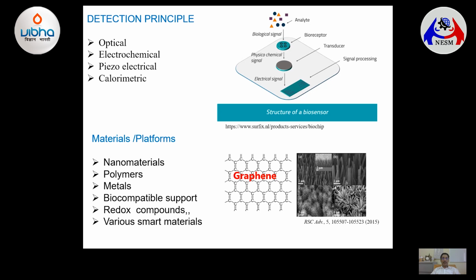This signal may be optical, electrochemical, piezoelectric, or calorimetric, and it is ultimately transduced to an electrical signal, which is then processed and finally appears in digital form to show the quantity of the analyte present in a sample. Based on the type of transducer, biosensors are generally classified. There are basically four different kinds of transducers. One is optical, another is electrochemical. Within electrochemical, there are different types, like amperometric, voltammetric, potentiometric, conductometric, and so on. Then piezoelectric transducers, which involve change of mass. Then calorimetric transducers, which generally involve change of heat or enthalpy.